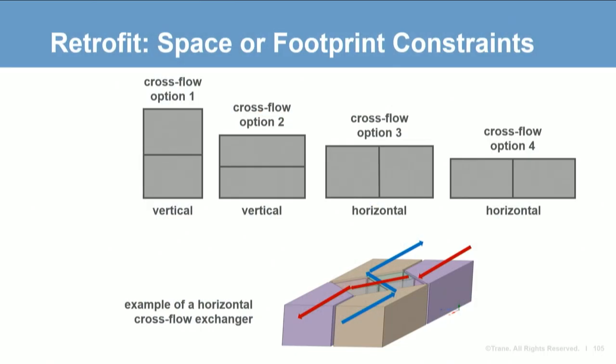SAM has a high velocity option that uses wider spacing to allow more airflow but sacrifices some latent recovery. Wheels also have a wider spacing media option allowing more airflow but with reduced sensible and latent effectiveness, though these options can sometimes help these technologies fit. Metal plate exchanger, membrane, and SAM can all be configured in either a vertical or horizontal orientation and can be put together in different aspect ratios. A wheel cassette is square, so whether airflows are side by side or top and bottom, the dimensions won't change.